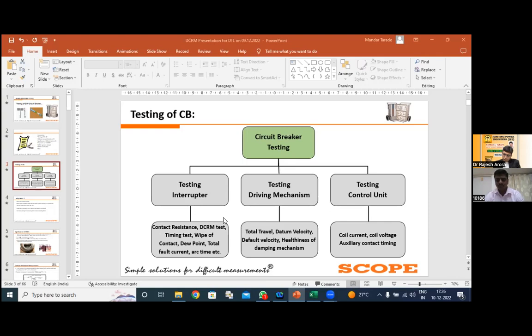Further moving ahead, we perform the testing of the control unit. In the control unit, basically we perform the test on the coil current and the auxiliary switches. As all of us know, the coil is energized to actuate the mechanism, and the auxiliary contacts are always connected in series with the coil for protection purposes. So by performing the test on the control unit, we can comment on the health of the auxiliary contact as well as the coil current.